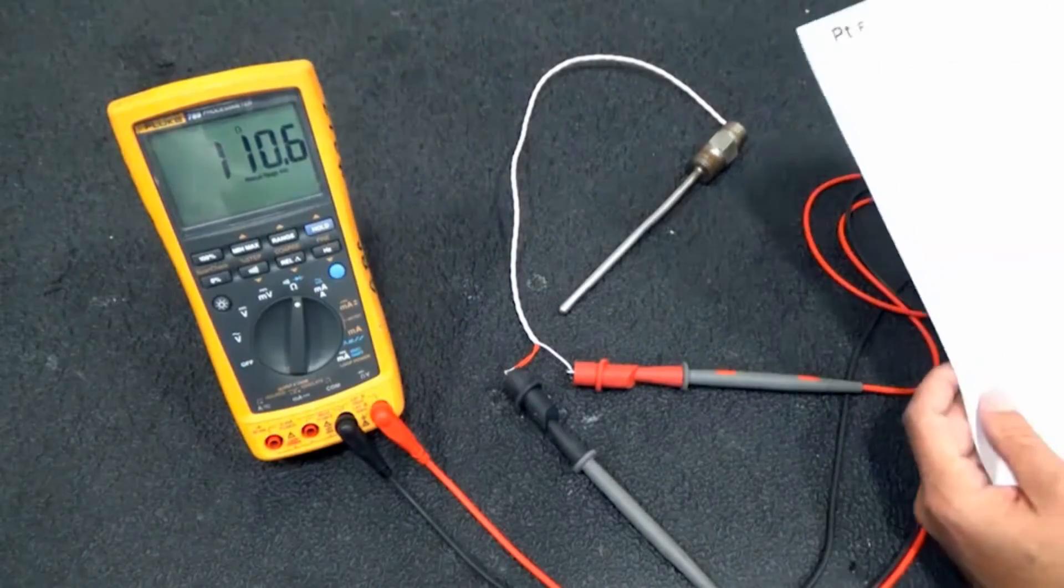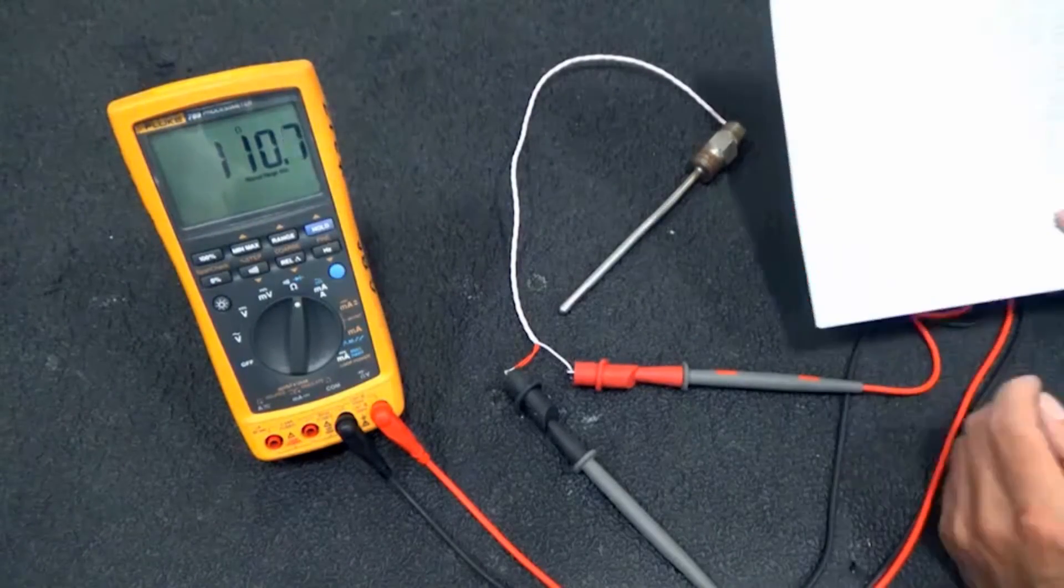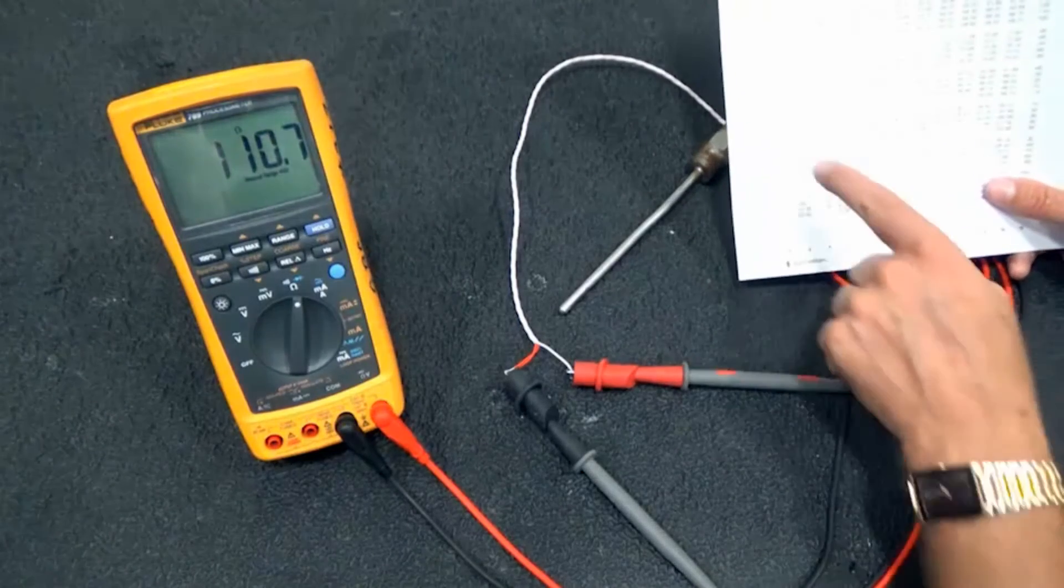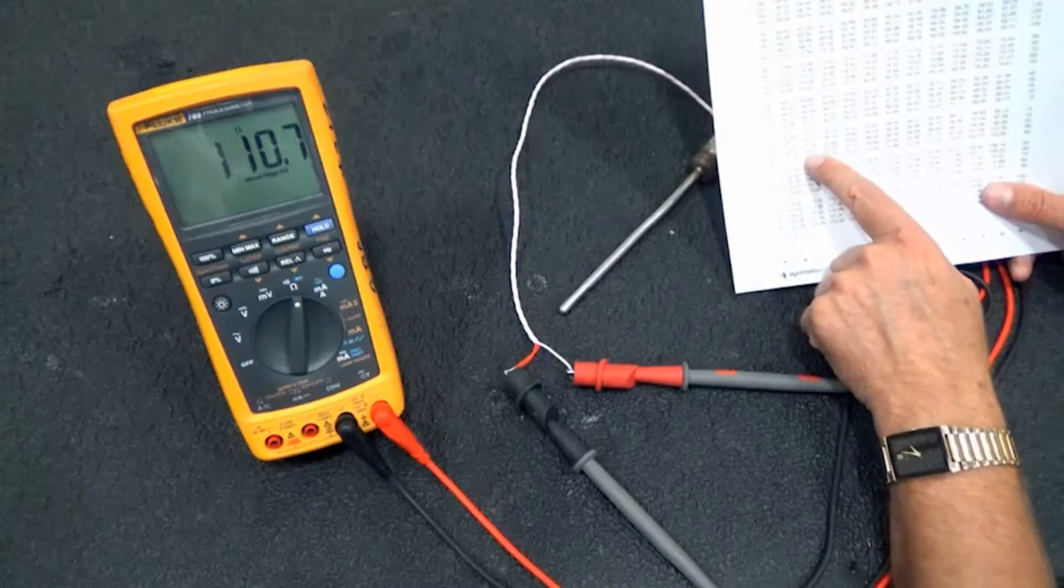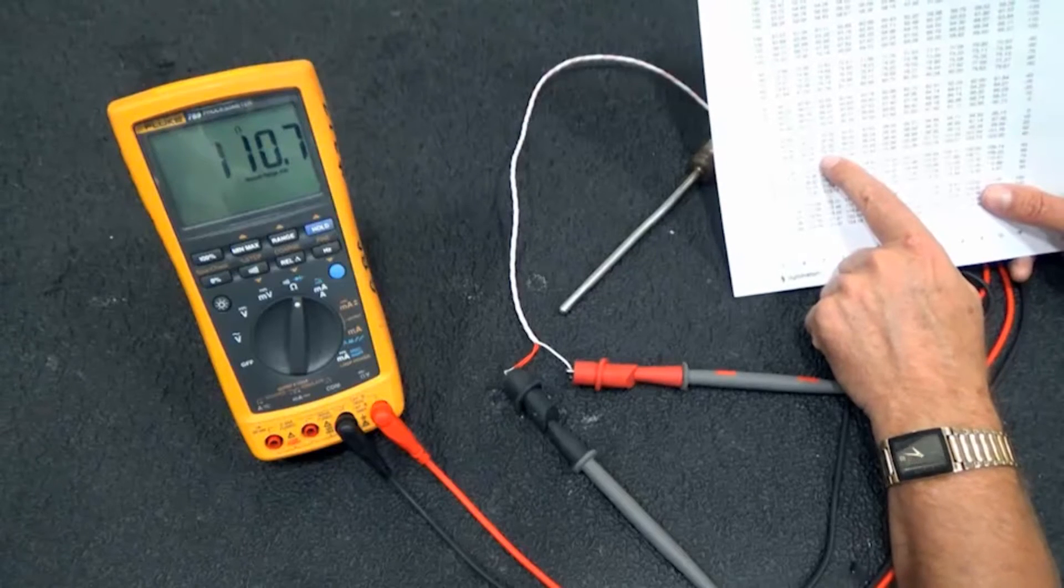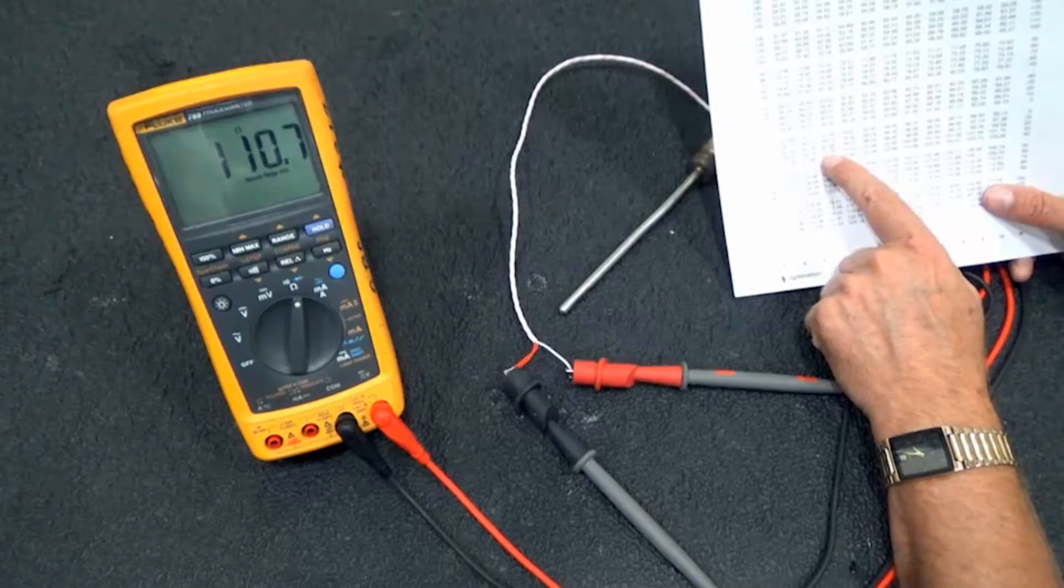The one remaining thing would be to check the calibration of this RTD, and we would immerse it in an ice water bath, and it should read 100 ohms.